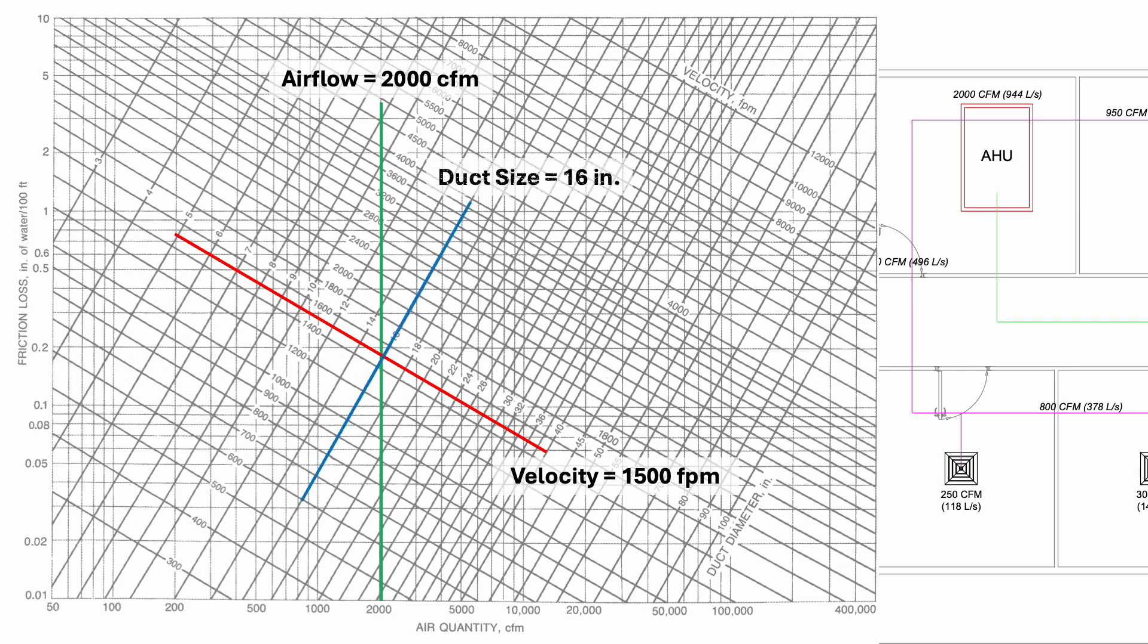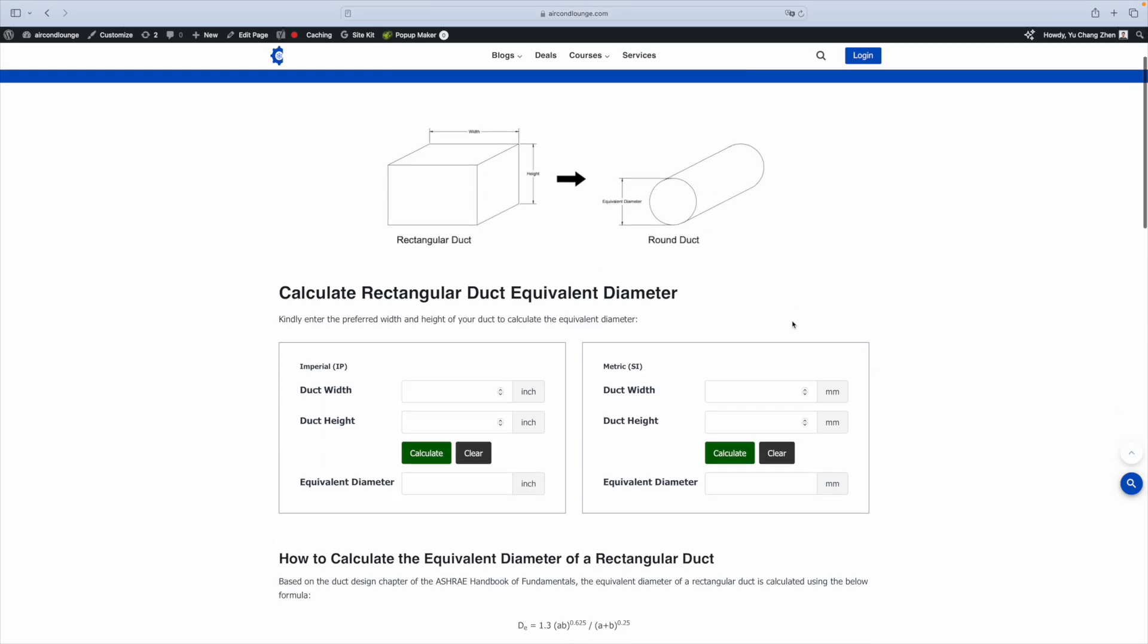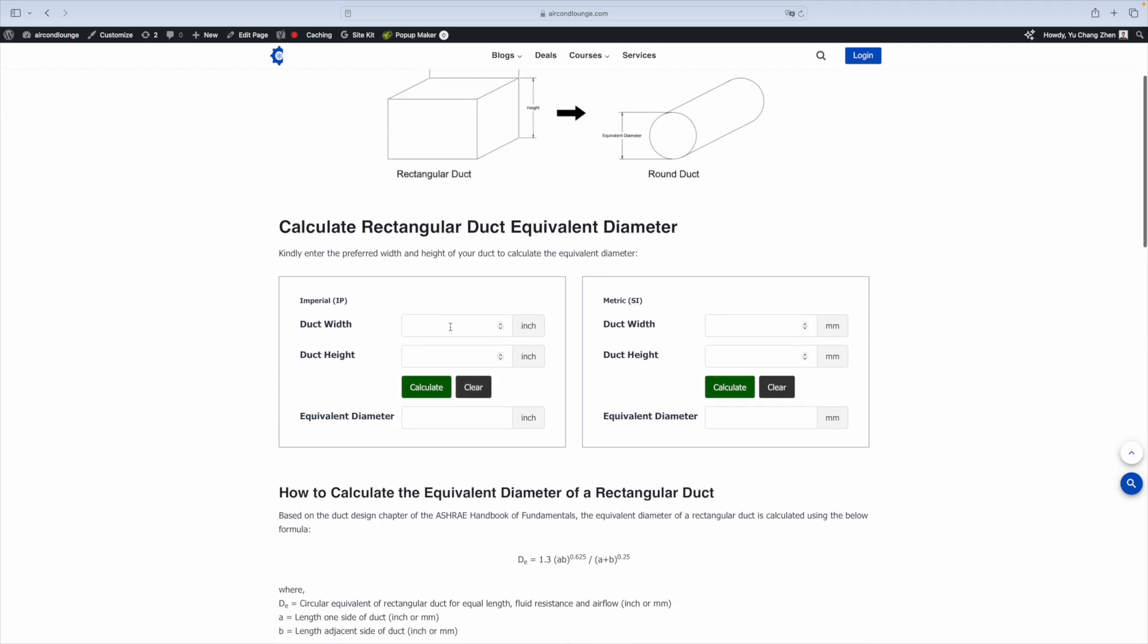As a result, our duct size is 16 inch. If you are designing for houses in the United States, you might want to follow the ACCA standard which is 900 feet per minute for supply duct and 700 feet per minute for return duct. The friction loss chart gives us the duct size in diameter. If we want to use rectangular duct, we need to calculate the equivalent diameter. We enter the duct width, duct height and press calculate.